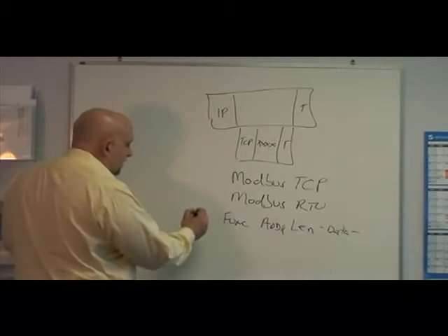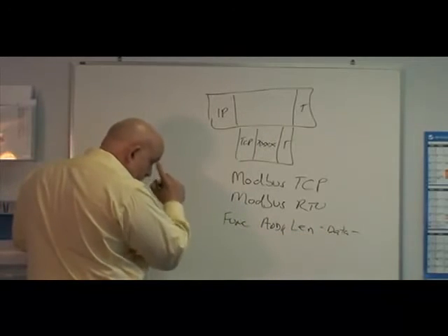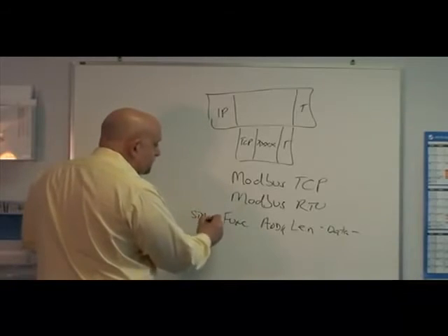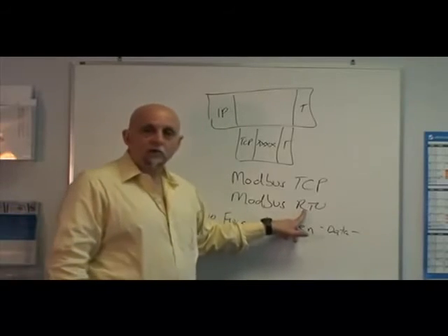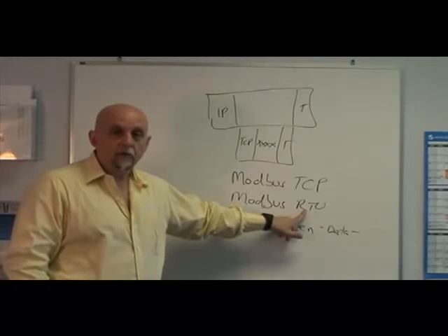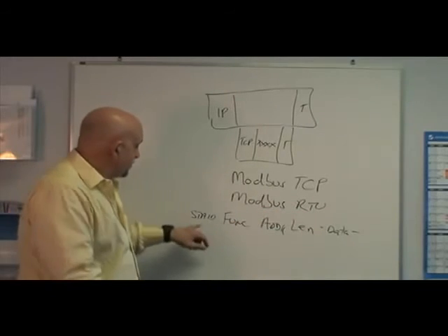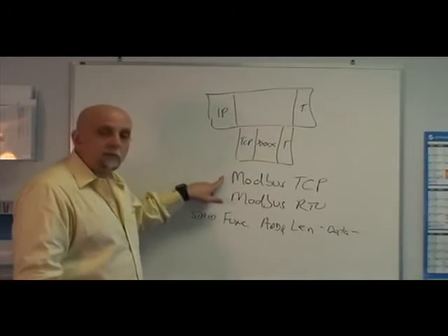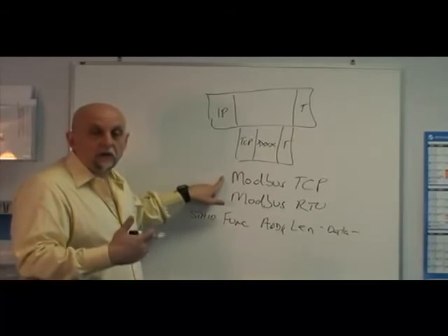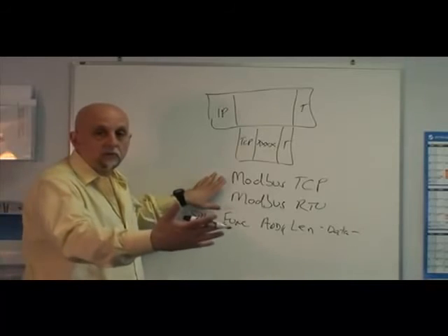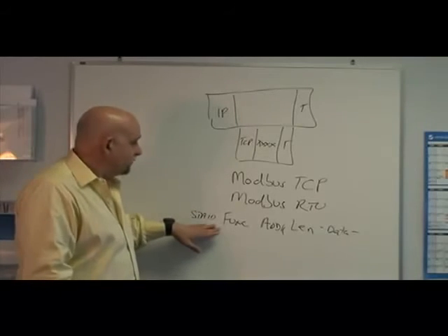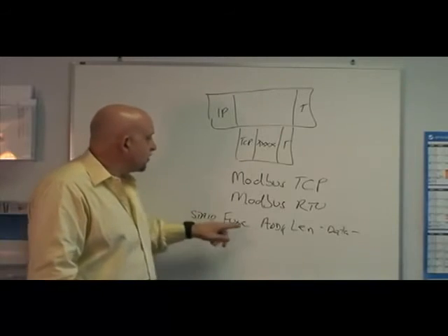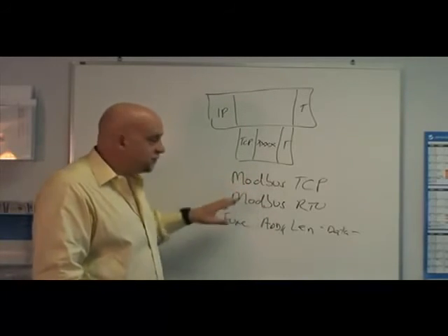Now, Modbus RTU is the same kind of message structure. It's actually got an address on the front, a station ID on the front, because Modbus RTU is on RS-485, so that's a multi-drop network, so you need a station ID to indicate which particular device. On Modbus TCP, we don't use that because we've got an IP address. We've made a connection with a specific IP address. On 485, you have to identify the station it's going to. So that's really the only difference between it.